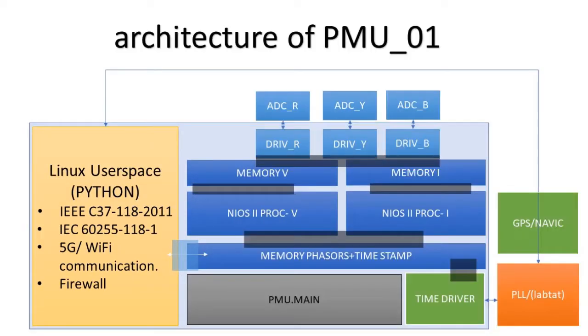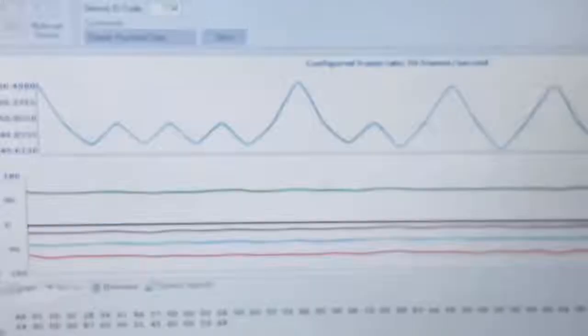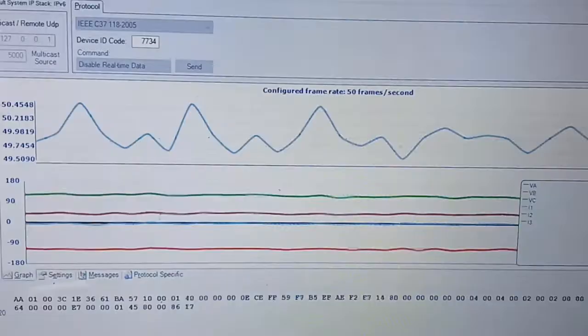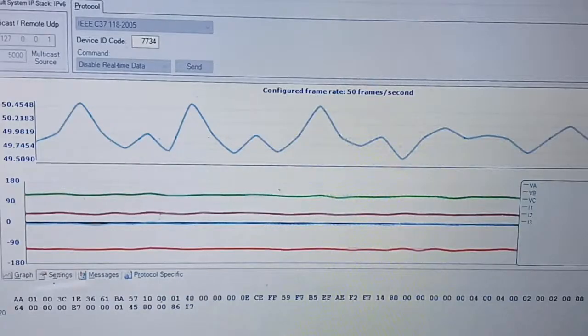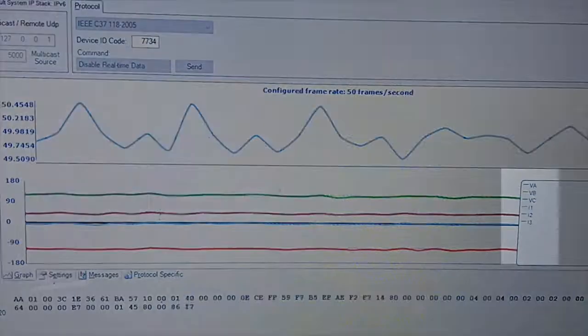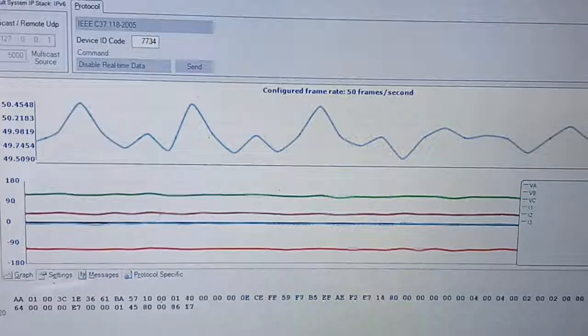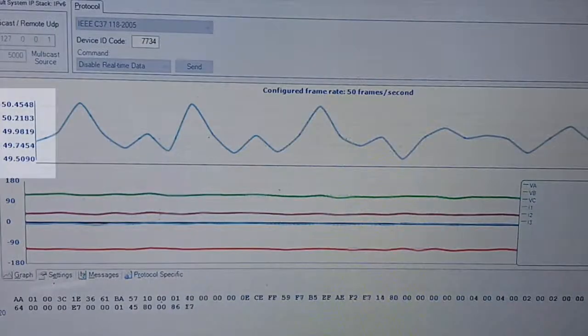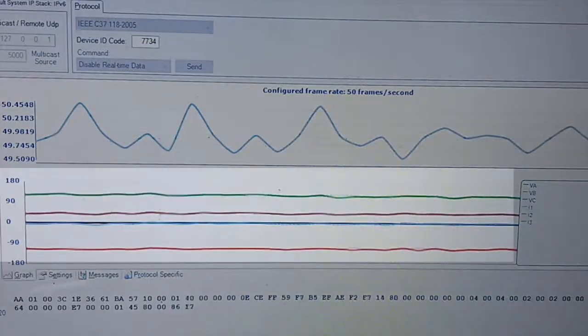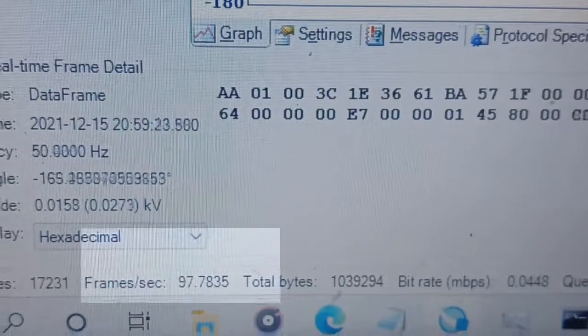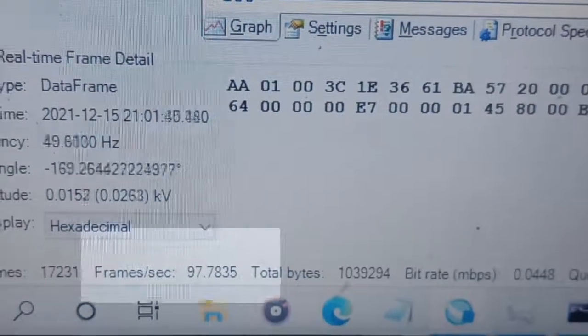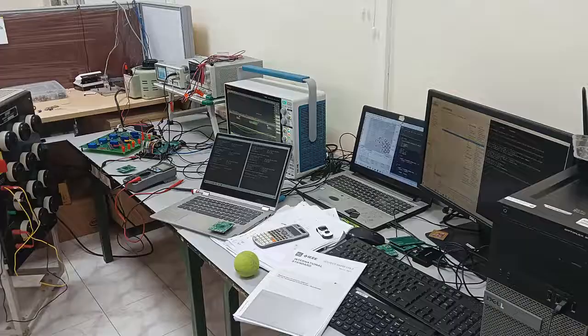The process of sample collection, processing and communication continues to run in-loop. This is the demonstration of micro-PMU at IIT Kanpur reporting phasor data to PDC. It shows total six phasors, frequency around 50 Hz and phase angle 120 degrees apart, and here 100 frames per second showing 97 currently.